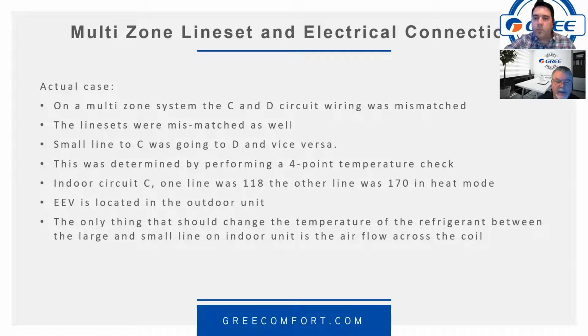Yeah, because the fan blowing across the coil, the refrigerant's going to pick up heat. There is going to be some temperature difference, but it's not going to be 118 and 170. And let me clarify, on the Flex, it was PSI difference, not temperature difference. On the mini splits, we're talking temperature difference. Right.